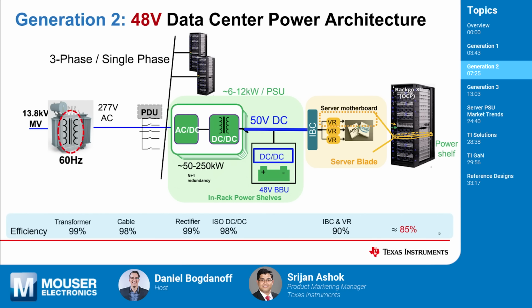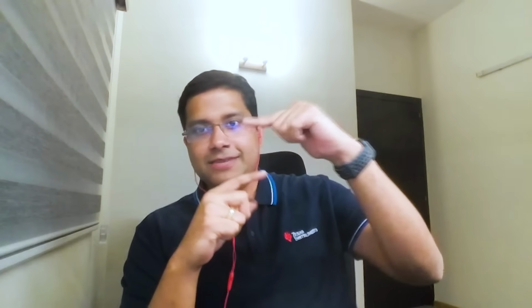Some folks might ask, why 48 volts? Why not go to 96 volts or 200 volts or something even higher? Well, from a safety perspective, 60 volt DC is considered safe for humans, and 48 volt has some buffer below that 60 volt level. So it sits there such that if there are spikes, nothing exceeds 60 volts - it's safe for human handling. That's the reason 48 volt got chosen as a power level. Now, coming to how the efficiency also works, one thing I already mentioned is the I-square-R component.